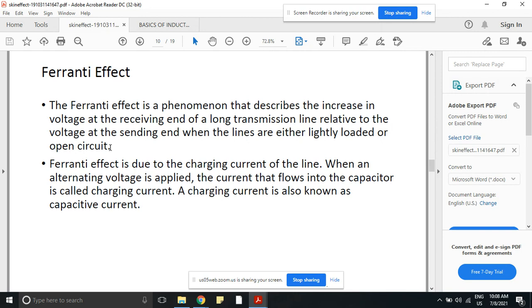So the Ferranti effect, by definition, states that in case of a long transmission line which is lightly loaded or no loaded, there is a phenomenon where the receiving end voltage will be greater than the sending end voltage. Usually, whenever you send, say, 100 kilovolts from the sending end side, the receiving end side voltage will be lesser than the sending end voltage because of the drop observed in the transmission line. So how do we calculate the drop in a line?